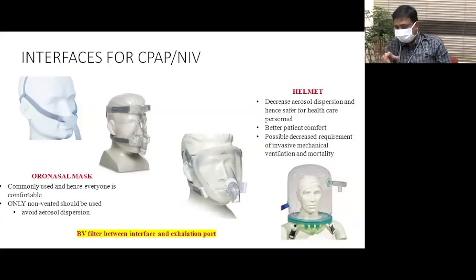Then moving on to the full face mask, which we see as the third one here. Again, because of irritation and flow into the eye, it is not a preferred mode. The helmet is a mode that has been projected to have less aerosol dispersion, be safer for healthcare workers, and give better patient comfort. So we have tried it in a reasonable number of patients during the first wave of the pandemic, but it has its own limitations in terms of connections to the BiPAP machine, the ventilator, and so on, and people are not familiar with using this. So unless you're geared to go that way, that may not be the right option. So the oronasal mask will be the conventional mode of delivery.